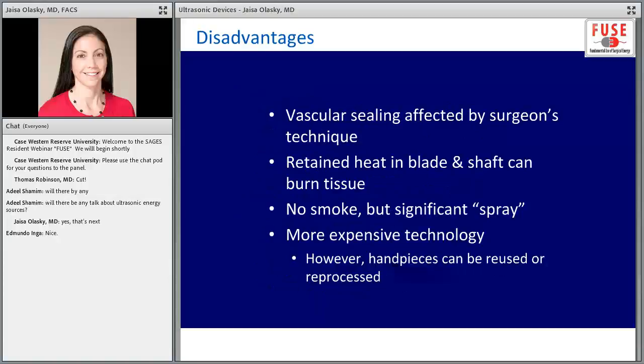However, overall, some of the disadvantages: the vascular sealing is affected by the surgeon's technique, so you have to really keep the jaws closed and have the true coaptive coagulation for vascular sealing. In addition, the retained heat in the blade and shaft can burn tissue when you go to use the device again. Although there is the advantage of not having smoke, there is significant spray, so it can make visualization difficult if there's a lot of spray. Also, it's a more expensive technology, so while the handpieces can be reused or reprocessed, at the same time, this also can contribute to blade fatigue and failure. So overall, if you're using newer instruments, it is very expensive. And one other disadvantage that's not on the slide is that some of that coagulum can build up on the blades, and then you have to activate it in saline or water in order to clear them off.